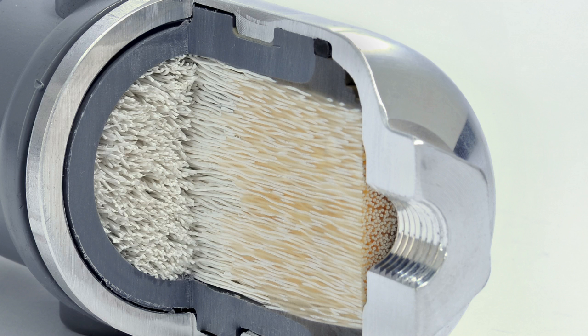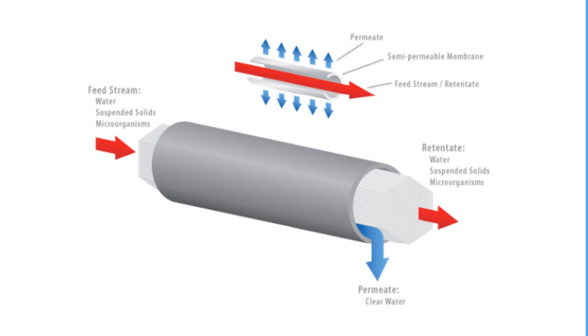Hollow fiber filtration utilizes thousands of long porous filaments ranging from 1 to 3.5 millimeters wide. They're usually potted in place within a PVC shell. Each filament is very narrow in diameter and flexible. Hollow fiber can also find uses in other types of filtration, ranging from microfiltration to reverse osmosis. Hollow fiber filtration works on the same principle as tubular and other capillary configurations, such as the spiral wound design, but utilizes small tube diameter, which allows for greater flexibility. Hollow fiber membranes feature a very high packing density because of the small strand diameter, and because of all this flexibility, certain filter configurations that are possible cannot be achieved in other filtration configurations.